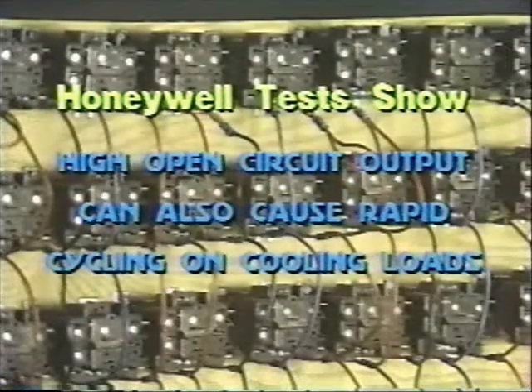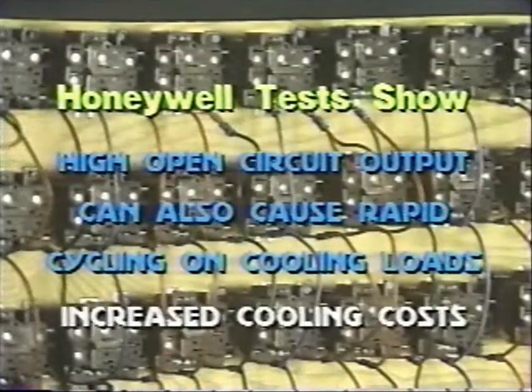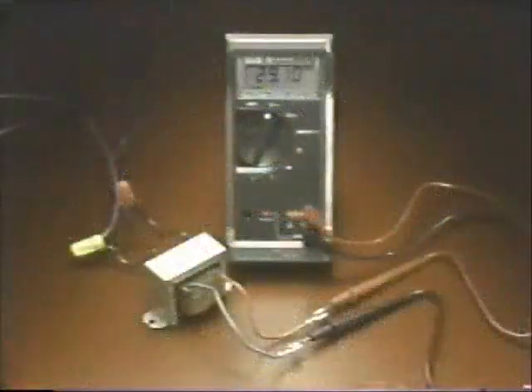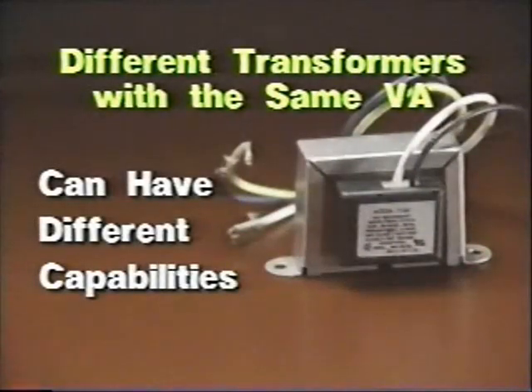Department tests show that high open circuit output voltage can also cause the thermostat to cycle the system too rapidly on cooling loads, because of increased cooling anticipator heat output. The result can be overcooling and increased cooling cost. Some systems require a 26-volt open circuit, and if you hit them with 29 or 30 volts, the system's logic may lock up intermittently. If you run into a situation where open circuit voltage is up near 30 volts, you may also find that its voltage falls off very rapidly as you load it down. The key point here is that different transformers with the same VA rating can indeed have quite different capabilities.